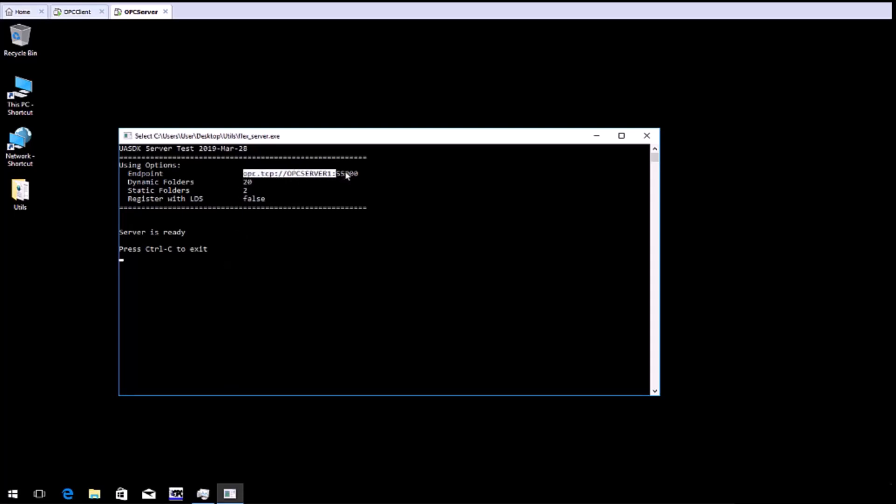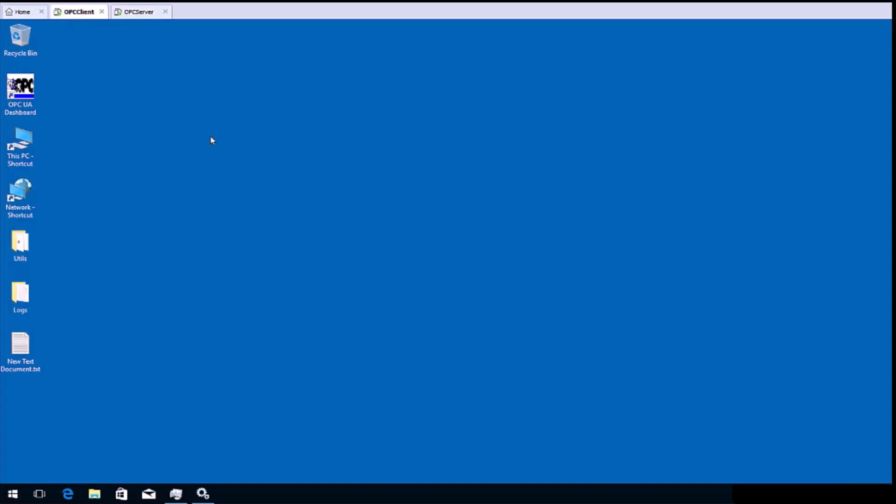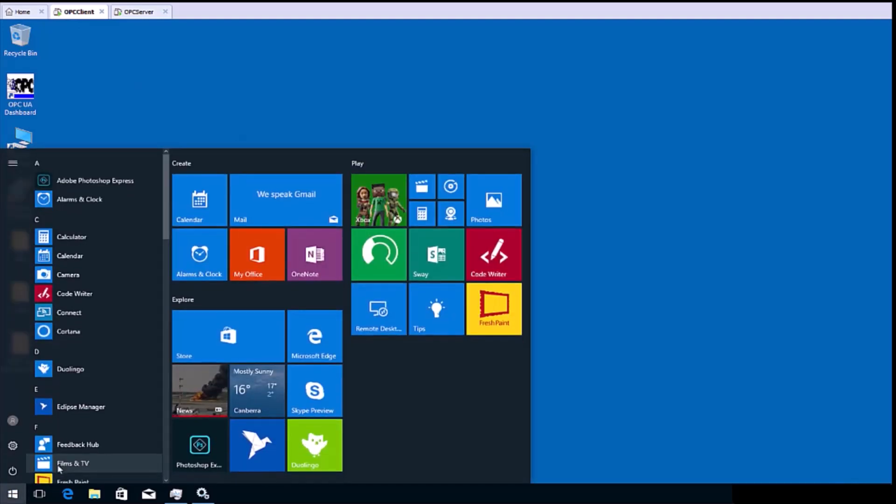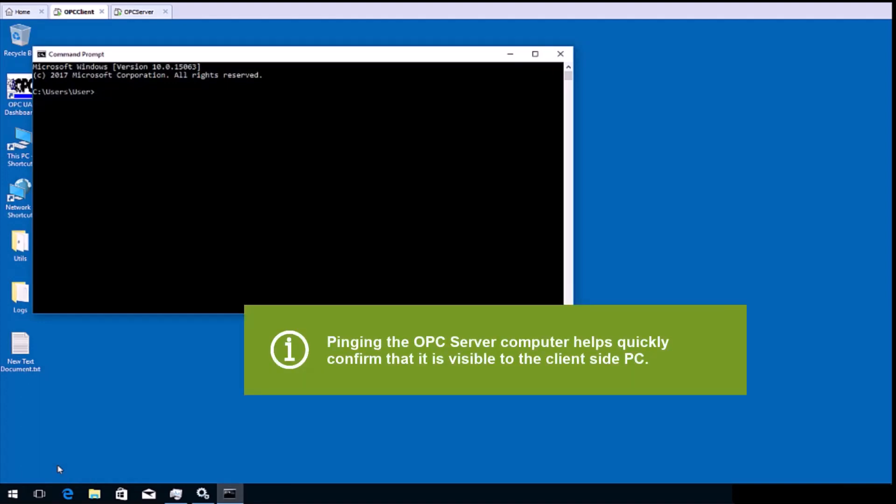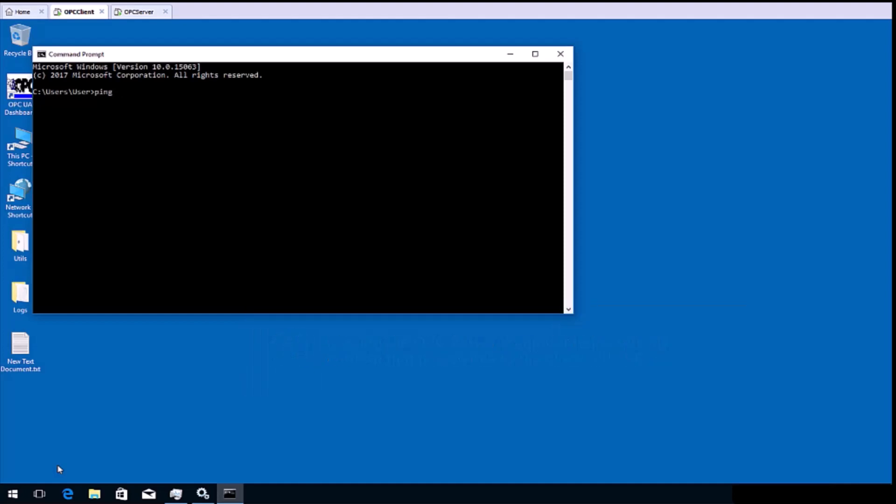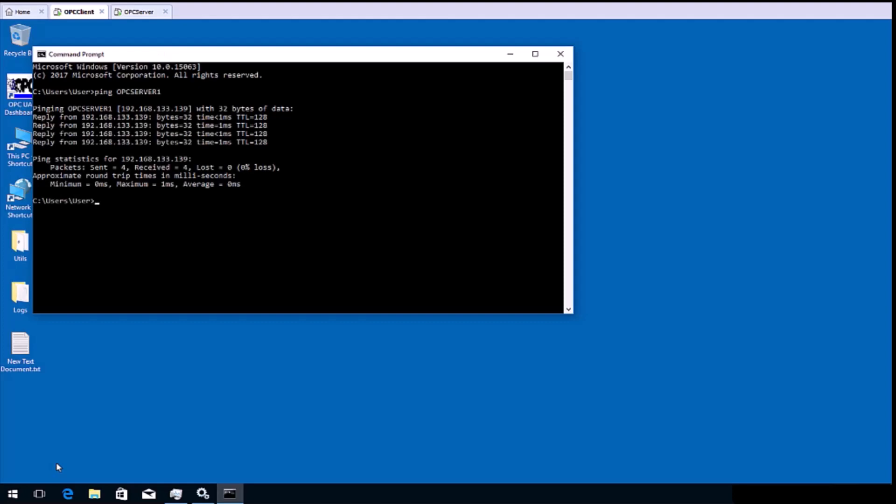We will now move to the computer that has the classic OPC client and Tunneler on it. Start by opening a command prompt and try pinging the remote OPC UA server computer. In this case, mine is called OPC Server 1. And we can see there a successful ping test. If this fails, contact your network administrator. Once the successful ping test has been confirmed, open the Matrikon OPC UA Tunneler configuration panel from the Windows Start menu.